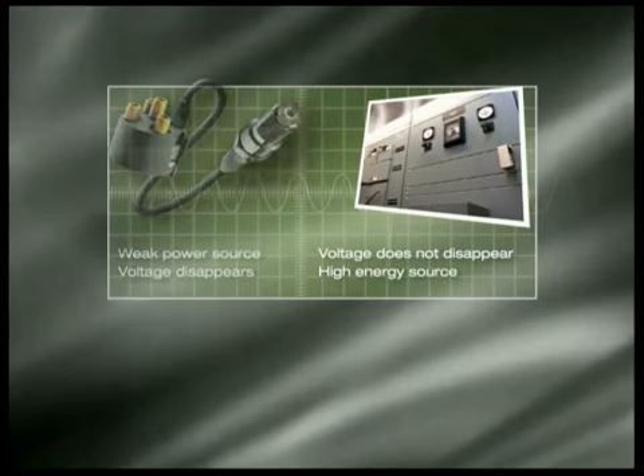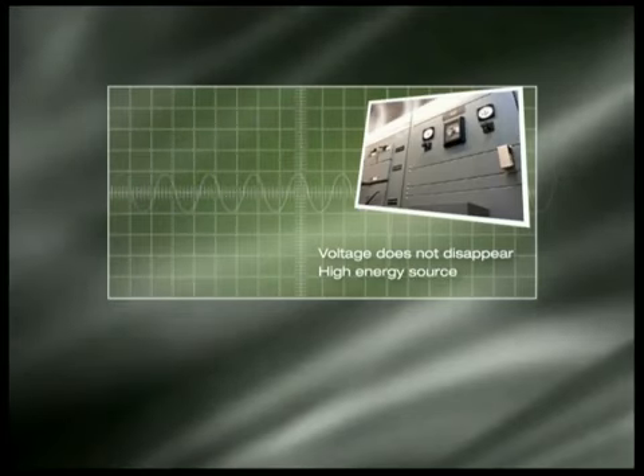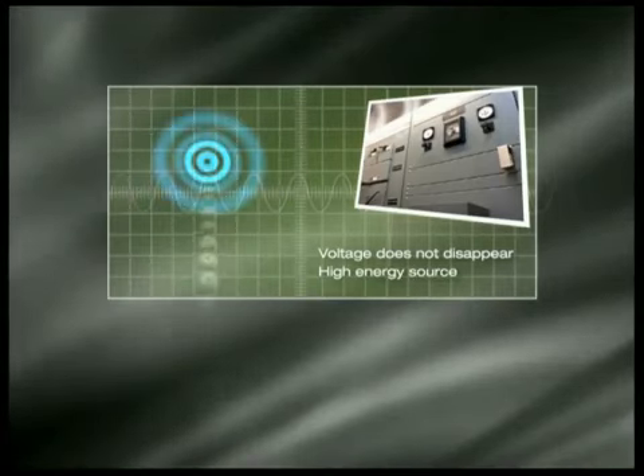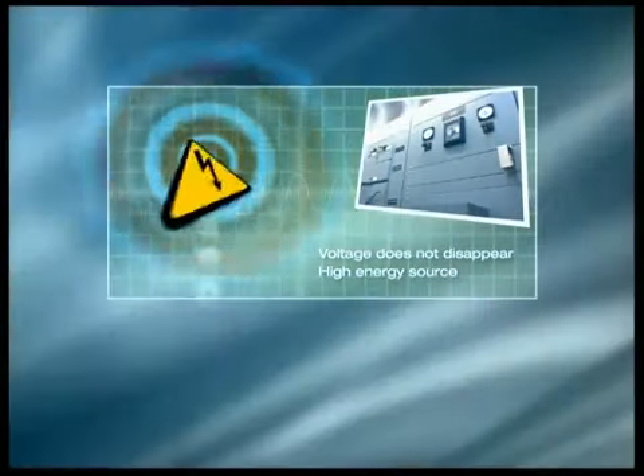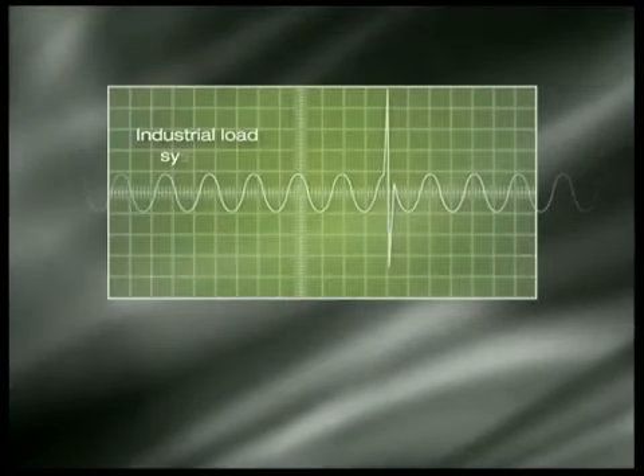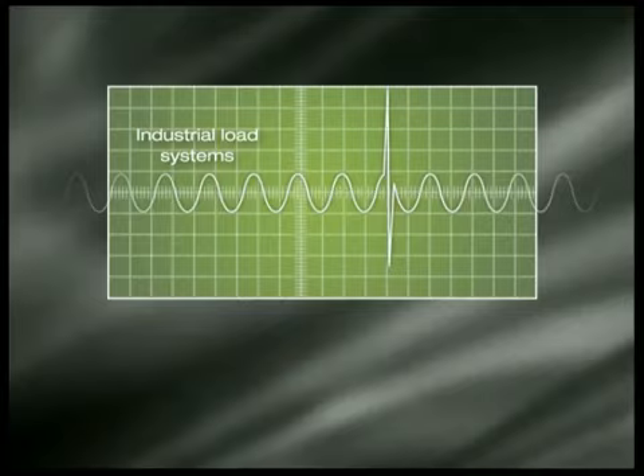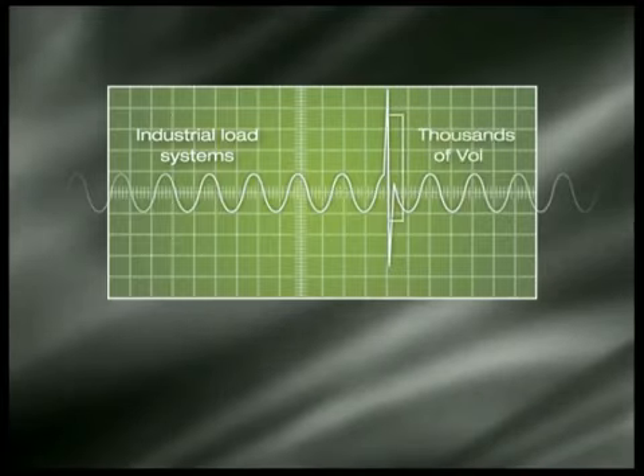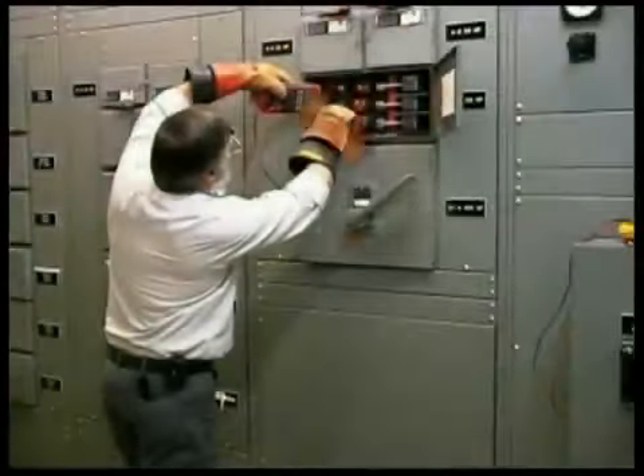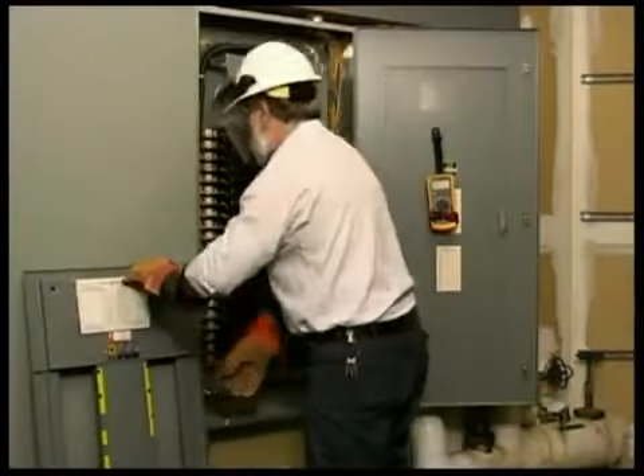And because the circuit is a high-energy source, it can supply current to the spark until the surrounding air breaks down into conductive plasma, causing a major fault. When transients ride on top of the system voltages that supply industrial loads, they can reach thousands of volts, and the consequences can be devastating, particularly for anyone taking measurements on electrical equipment.